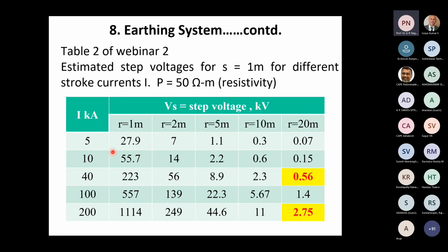Now, the step voltage here for 5 kA at 1 meter distance is 27.9 kV for R equal to 1 meter. Similarly, if you think of a 20 meter radius, the step voltage becomes only 0.07 kV, that means 70 volts. Consider, for example, 40 kiloamperes, which is the sort of 50% probability current. The probabilistic distribution of currents is a very important parameter to look at. In the literature, 40 kiloamperes or higher has a 50% probability. The step voltage is 0.56 kV, that means 560 volts, which is again quite small. For 200 kA, it is 2.75 kV, which may still be thought of as safe. So if you think of this ring conductor as equivalent to a hemisphere of radius 20 meters, you will find that these step voltages are all pretty safe.